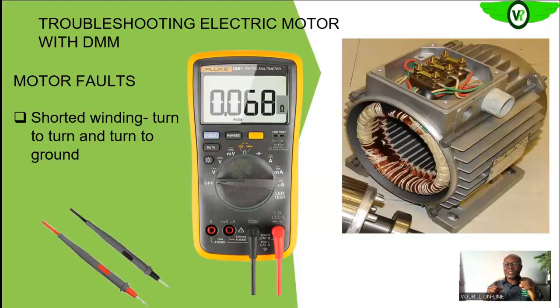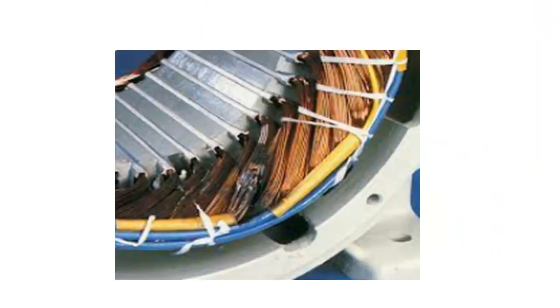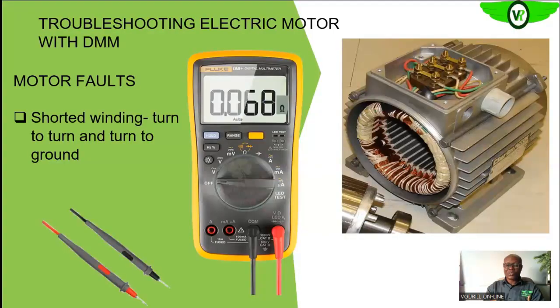Once they are different, that can cause rubbing of your rotor and further aggravate the problem with the electric motor. So a turn-to-turn short is not desirable in your electric motor. Apart from that, it also has some safety implications, because a turn-to-turn short can cause arcing at the point of contact, at the point of short, and eventually it can lead to burning, and that will lead to other catastrophic problems downstream or upstream in the electric circuitry.